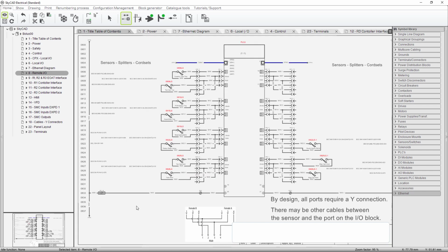Okay, with remote I/O, we've got an Ethernet connection. You can see it right up at the top, and you can see it's daisy chained. We got Ethernet coming in and Ethernet going out. Then there's electronics in here that gather up the state of all 16 of these inputs. Notice there's 8 connectors, and each connector has a T or Y or splitter on it. And you can connect up 2 sensors, 2 inputs to each input port.